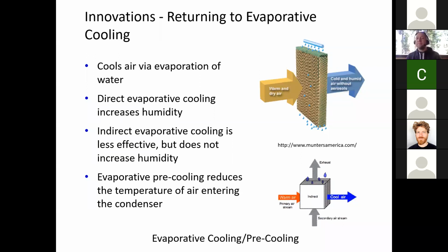The first airstream is the one we're trying to cool down, and we run it through a heat exchanger along with a second airstream, which is the one we add moisture to. That secondary airstream gets cool, and as it passes through the heat exchanger, our warm primary air is cooled by it - so we get the effect of cold air without adding moisture to the primary airstream.